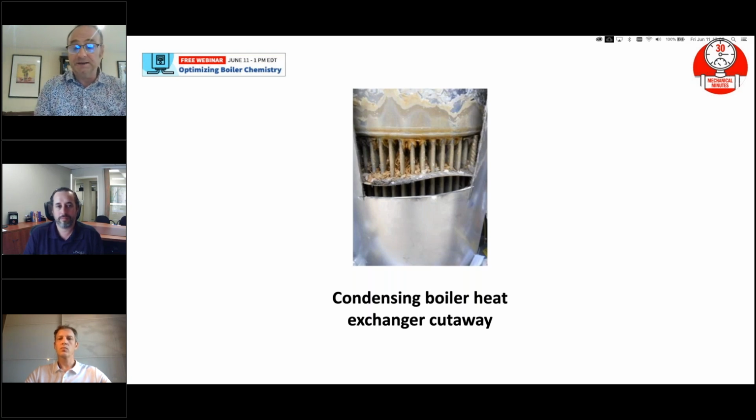Back in my day, the most important water treatment component was your air separator. Now, that's not the case. We want to test our water. We want to make sure that the pH is good and that the hardness is in line. If it's too hard, we're probably going to want to treat it. I know that a lot of places will order water from a water truck, soft water that doesn't have a lot of hardness or mineral in it. If you're hooking up to a municipal system, you can fill up your system through a cartridge or a system that will take the hardness out before it goes into the system.